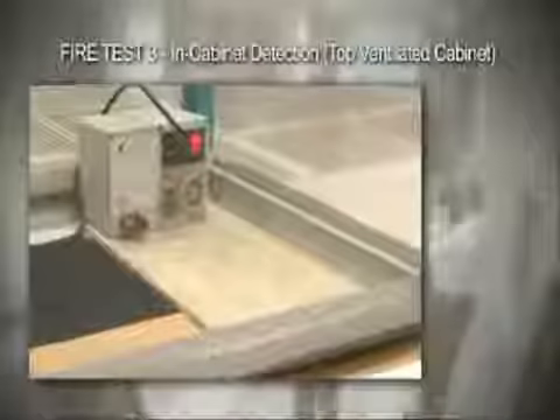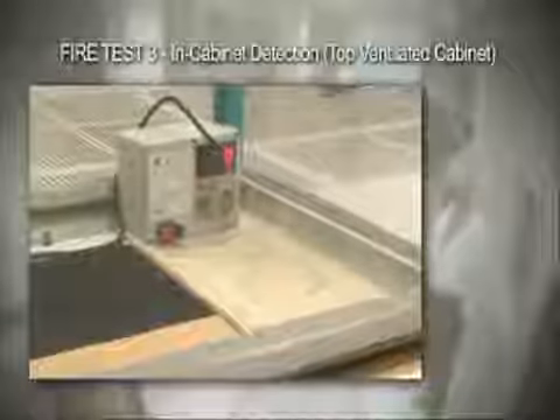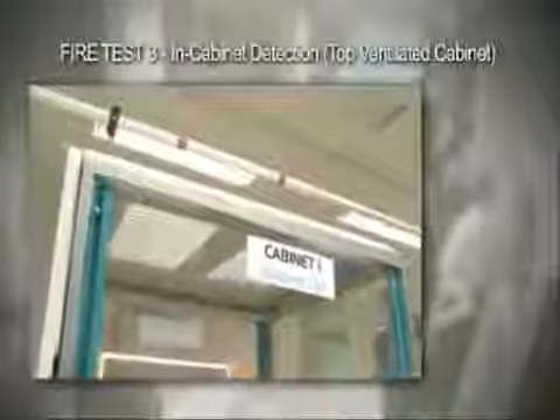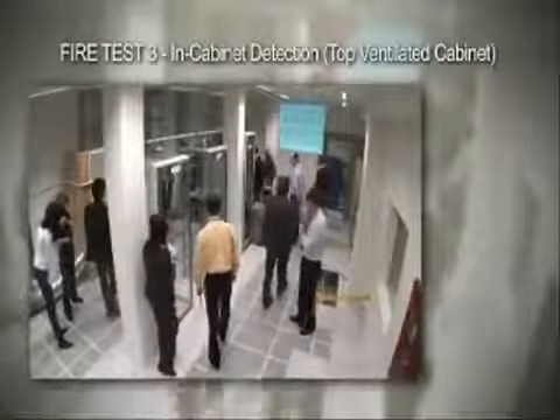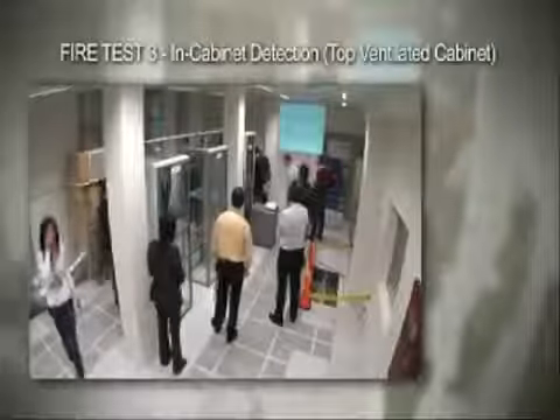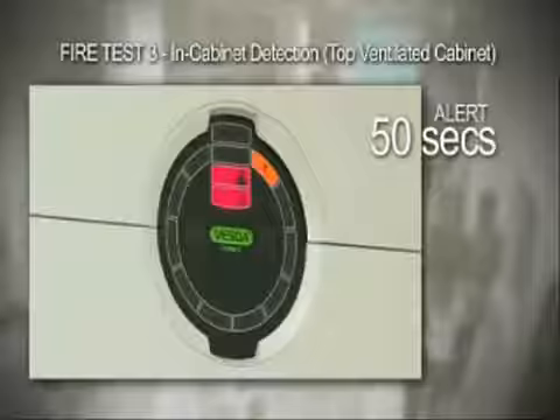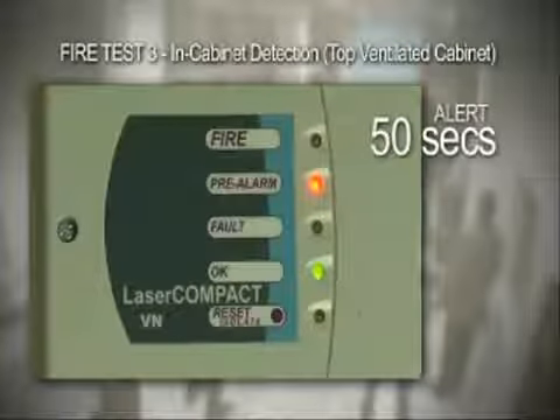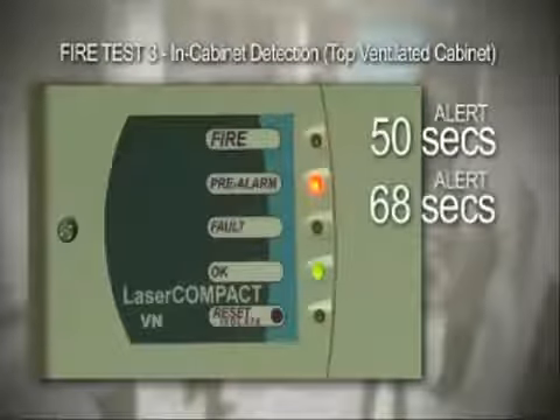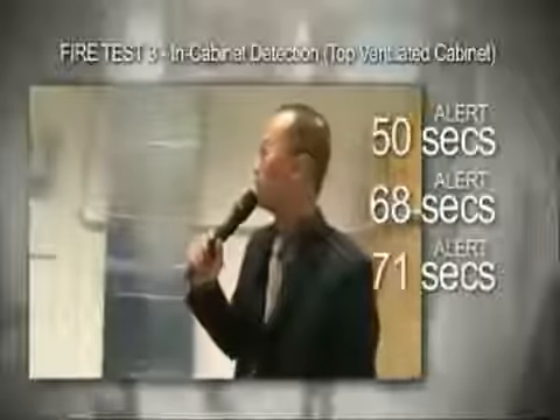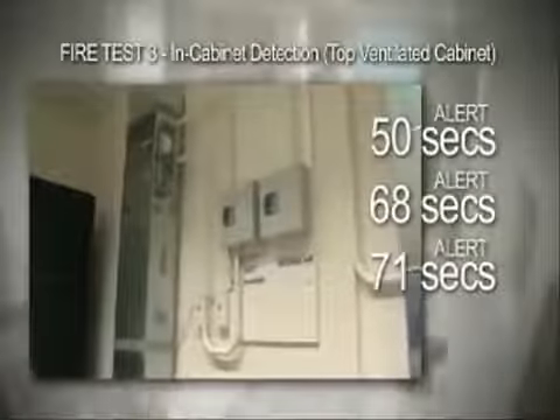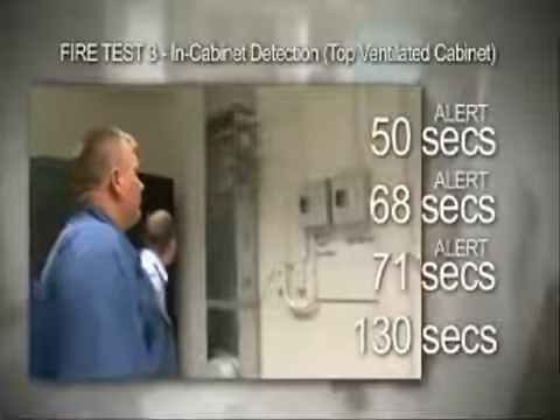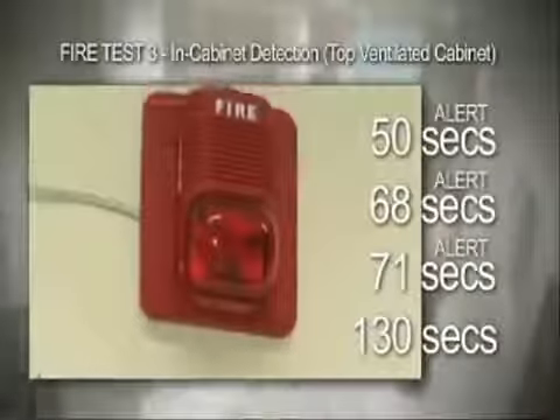Test 3 simulates an electrical component fire originating within a server cabinet that is ventilated from bottom to top. The VESDA sampling pipe is positioned across the top of the cabinet to detect the smoke as it is carried upwards with air currents. Point detectors are not positioned near the cabinets due to the negative electromagnetic effects on the server equipment. At 50 seconds, the VESDA Laser Focus detector across the top of the cabinet triggers the alert level. The VESDA Laser Compact detector, located across the return air grill, goes into alert at 68 seconds. At 71 seconds, the VESDA Laser Compact detector in the duct goes into alert level. After 130 seconds, the point detectors have still not detected smoke.